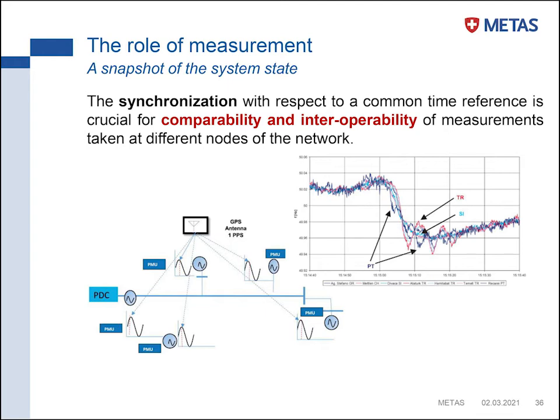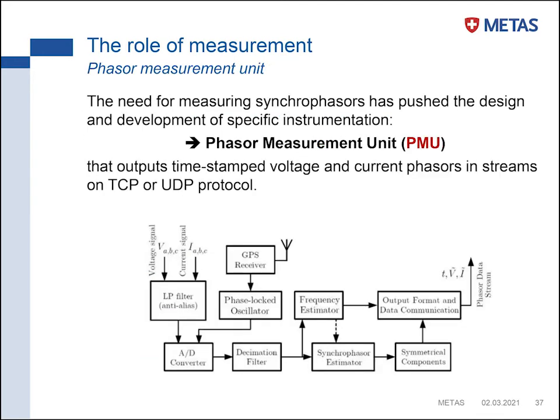Once we know what we want to measure, we need the instrument. The need for measuring synchrophasors pushed the design of a new type of instrument called the phasor measurement unit, or PMU. The first PMU was built in 1992, and essentially it's an ADC with a low-pass anti-aliasing filter that converts the voltage and current three-phase signals, performs computation to extrapolate the synchrophasor, and then outputs on Ethernet the voltage synchrophasor, the current synchrophasor, and the associated timestamp locked to GPS or PTP.